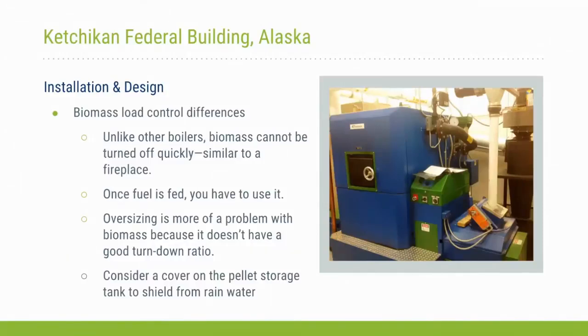Also, in hindsight, I have to mention Ketchikan in southeast Alaska gets about 140 to 150 inches of rain a year. And as we showed, the silo is directly outside in the elements. We do have a cover on top of the silo. However, it would have been a lot easier to put a better cover on top of that silo to prevent rain from getting inside the silo when we were filling it up. Moisture content of the fuel, wood pellet, is directly proportional to efficiency of the boiler, and it affects the heat output of the boiler as well. In terms of operation of the building and the boiler, I think Michelle Jones is more qualified to answer your questions and present it to you.